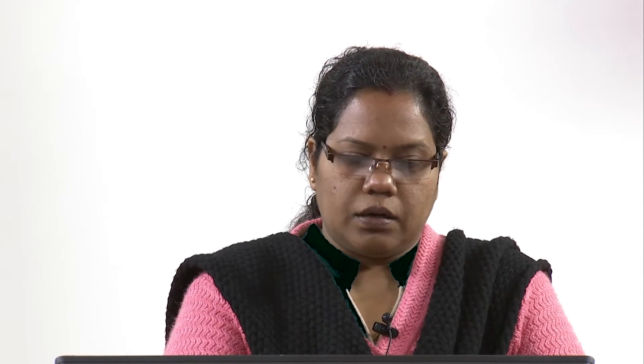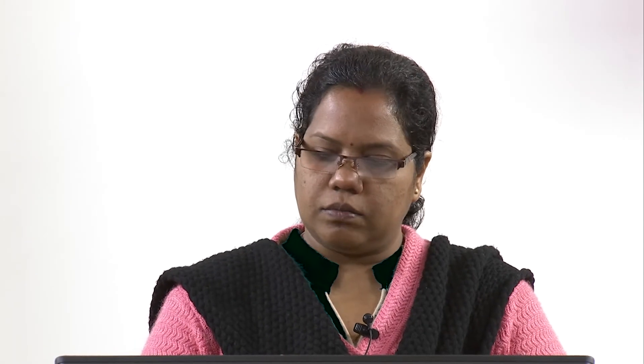Here, what we do is calculate the superimposed negative sequence impedance. The first step is to collect the three-phase voltages V_A, V_B, and V_C, and also the three-phase currents I_A, I_B, I_C at the terminal of the DGs or DERs. After getting these, we calculate the phasors at the terminal of the DERs using a least error square based technique, which can extract the fundamental even if the signal has a decaying DC component or harmonic components.